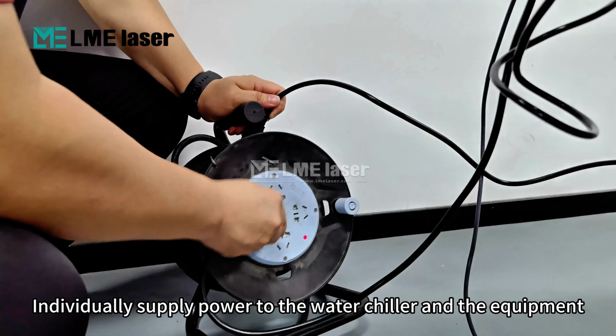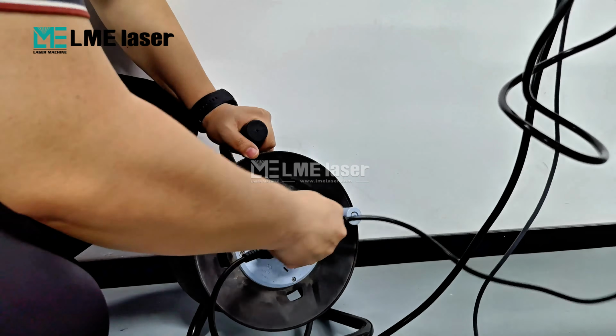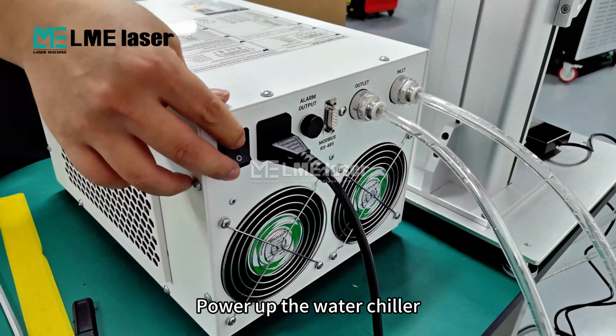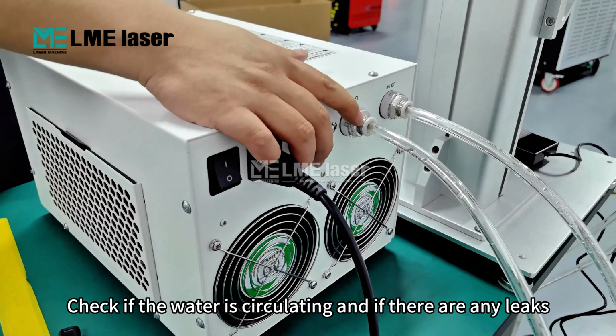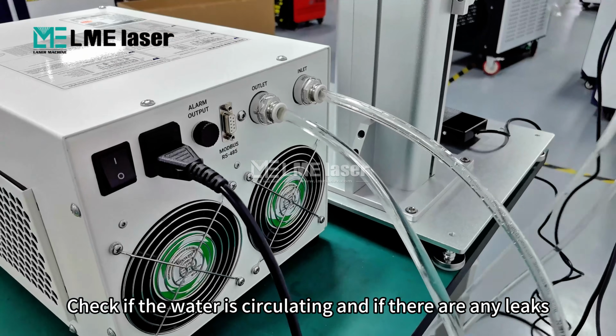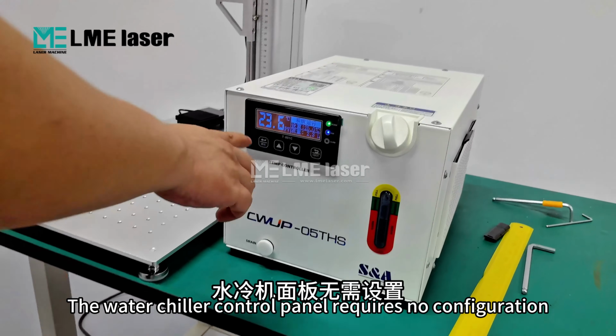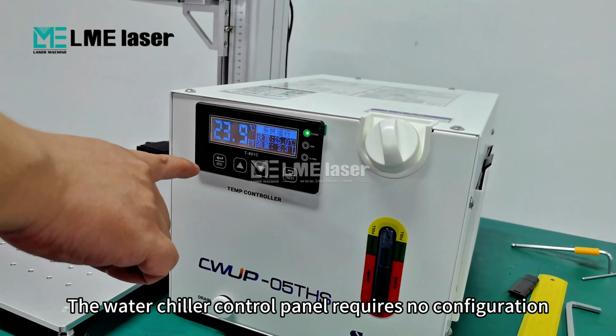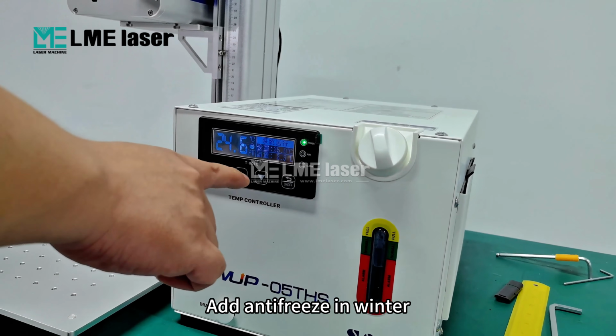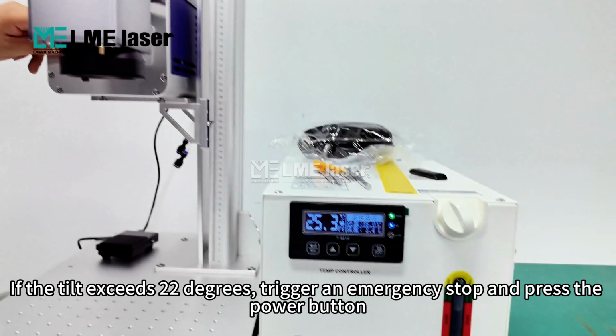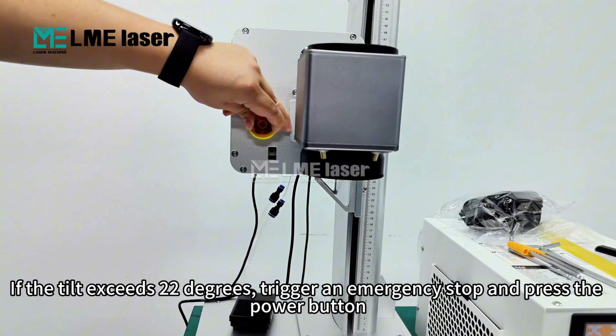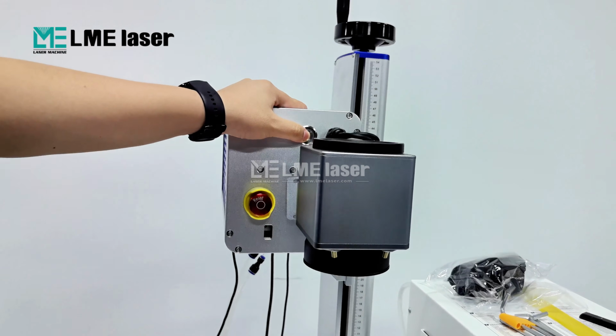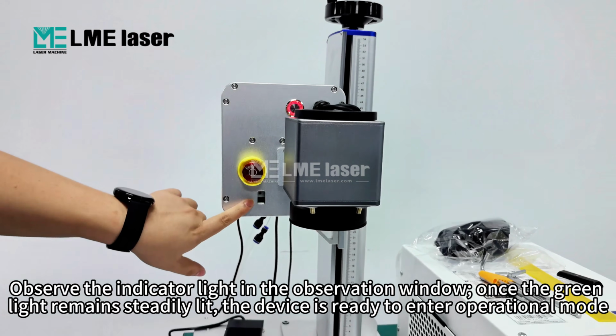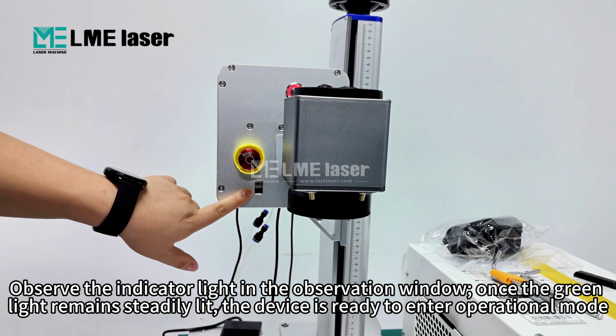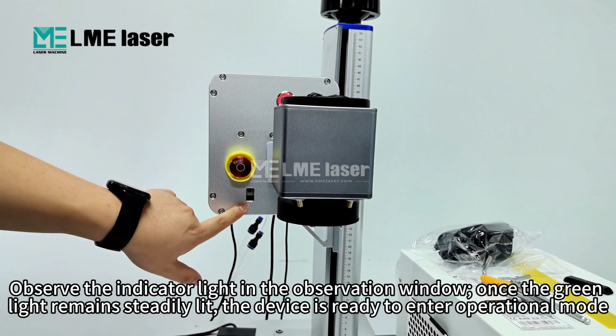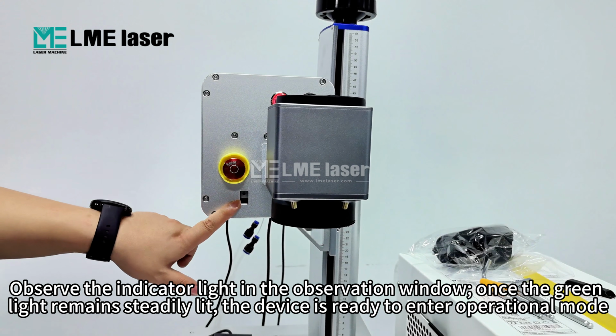Individually supply power to the water chiller and the equipment. Power up the water chiller. Check if the water is circulating and if there are any leaks. The water chiller control panel requires no configuration. Add antifreeze in winter. If the tilt exceeds 22 degrees, trigger an emergency stop and press the power button. Observe the indicator light in the observation window. Once the green light remains steadily lit, the device is ready to enter operational mode.